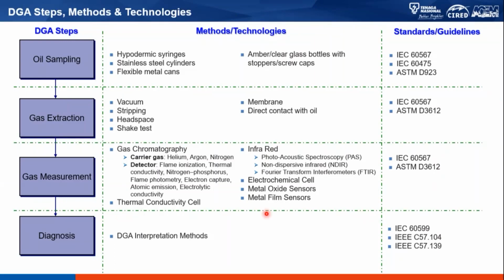For gas extraction, there are several methods as well. We are talking about vacuum extraction, extraction by stripping, headspace sampling, meaning the gases on top of the oil, and then the shake test, which was introduced by Morgan Schaffer, I think in 1993. There is also membrane technology, and direct contact with oil. Most of the time, this direct contact with oil is used to measure hydrogen or carbon dioxide.